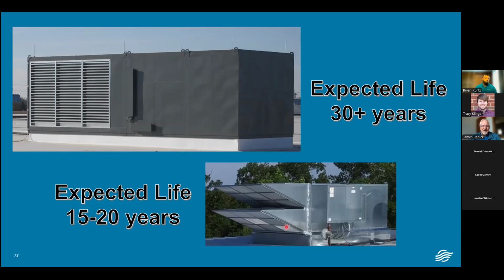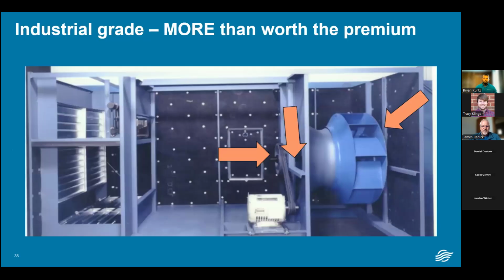And if you go into the next slide here, industrial grade, I like to say it's more than worth the premium. What you're looking at is a cutaway of the inside of that air management style air handler. I've got one arrow pointing to the fan shaft. For that, I wanted to show the bearings, because we use bearings in this equipment that are no less than L10 of 100,000 hours. And for many of the horizontal equipment, it's approaching more like 350 to 400,000 hours of life expected, with less than 10% of the product expected to fail.